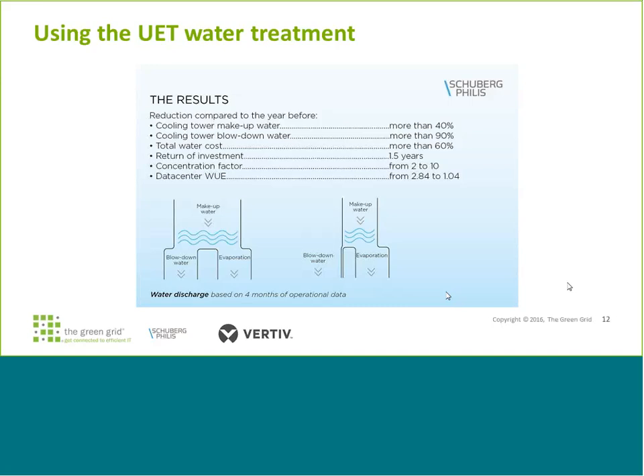Yeah, so the concentration factor, Frans is going to tell you something about that. That's more the chemical part of water. Yeah, the concentration factor is the amount of discharge that you have compared to the makeup water. So they used to have, for every 10 cubes of water, they would put 5 cubes an hour to the discharge, and if you compare it to the current situation, for every 10 cubes, you only have 1 cube an hour going to the discharge. So much higher efficiency, 5 times better than they did before.